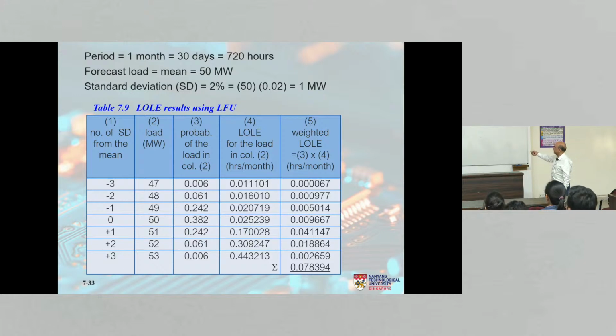Yeah, so the weighted value turns out to be 0.078. Do you remember the risk in the system when we did not consider any uncertainty in the load? The risk in the system was this, 0.025, correct? Now the risk in the system is 0.078, more than 3 times. So load forecast uncertainty must be considered. Here the standard deviation is 2%, maybe it's higher, and therefore this risk will also be correspondingly higher, right? So we have the tools, we know how to calculate them, we know how to include them in our analysis, yeah? So that's the question you were asking me the other day about uncertainty. So this is one way of modeling the uncertainty, okay?